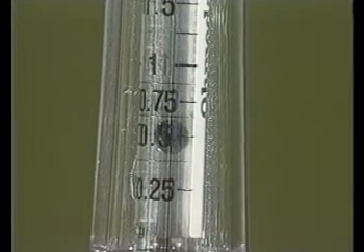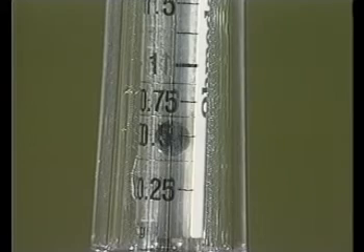However, the alarm whistle may not be effective at very low flow rates, under one litre per minute. The water in the humidifier should be changed daily. The humidifier should be washed and dried at least once a week, or when you stop giving oxygen to a patient, to avoid bacterial contamination.